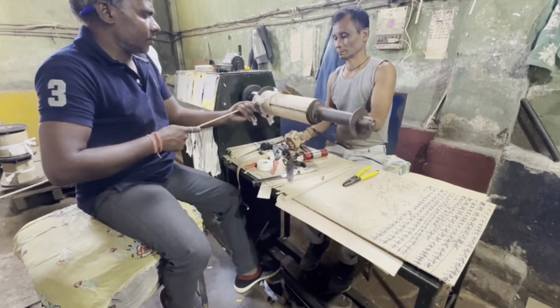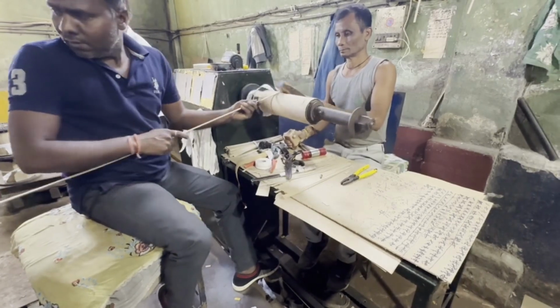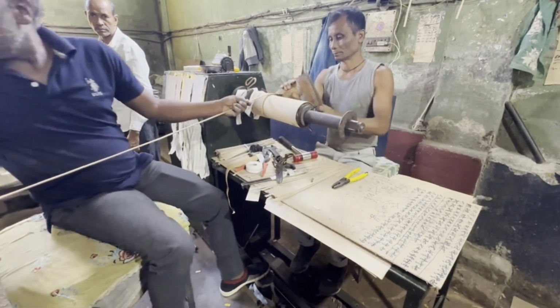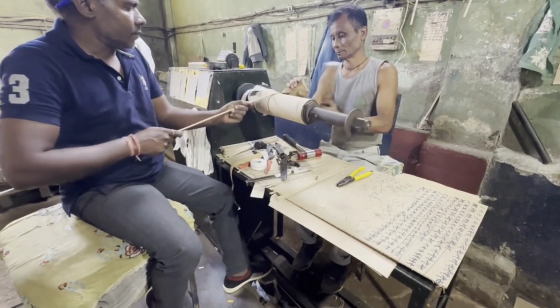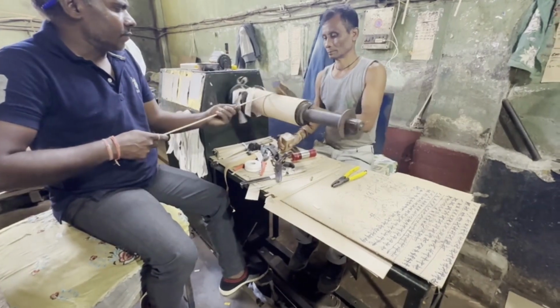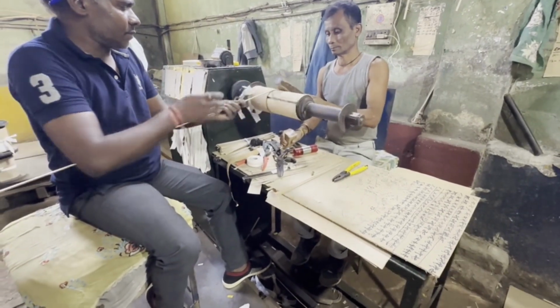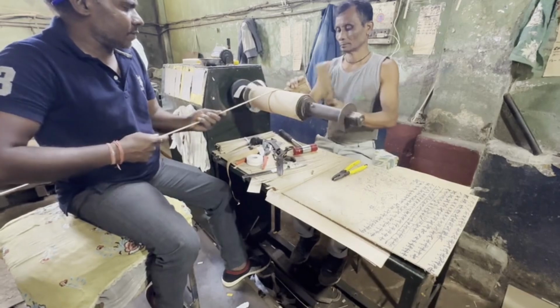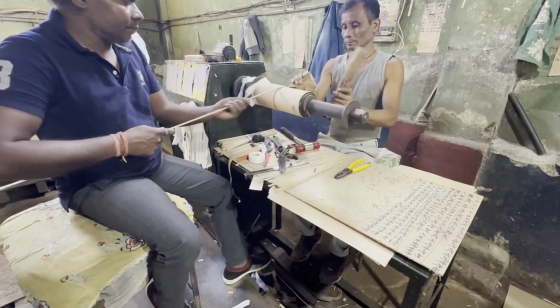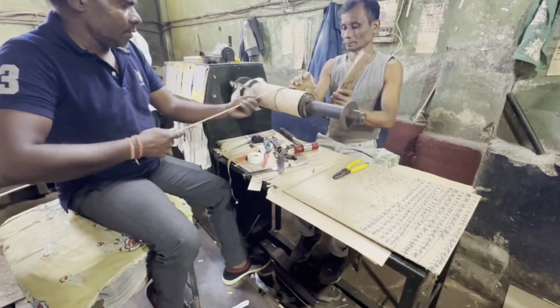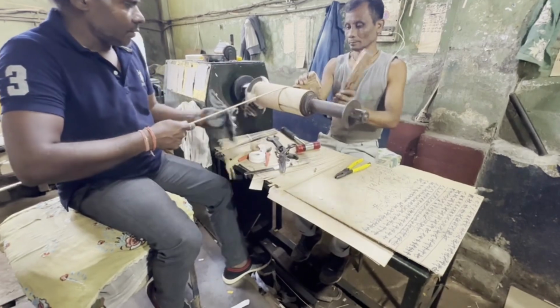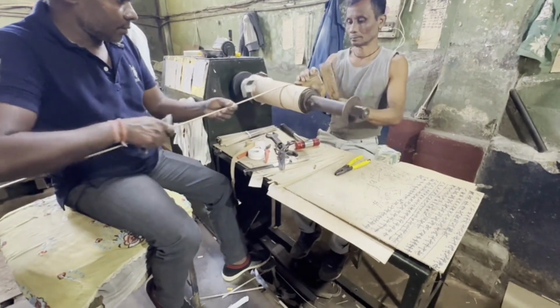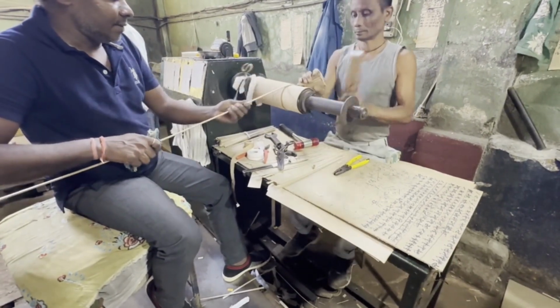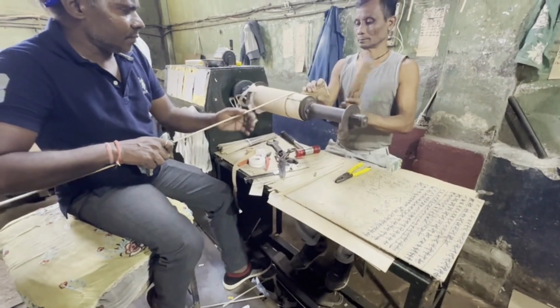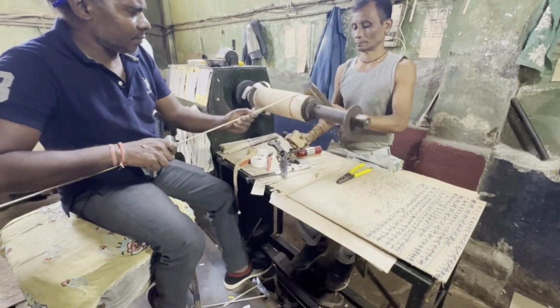Watch the coordination between the two operators. One controls alignment, the other manages feed and tension. This is machine precision, combined with human skill. What looks simple during manufacturing actually determines whether this transformer runs safely for decades. It will go through pressing and clamping. Proper compression locks everything in place to withstand short-circuit forces.